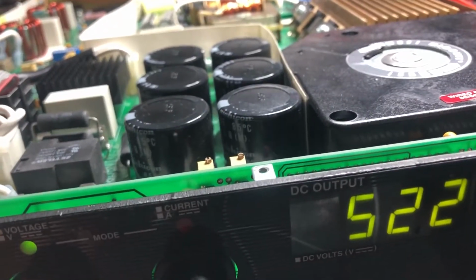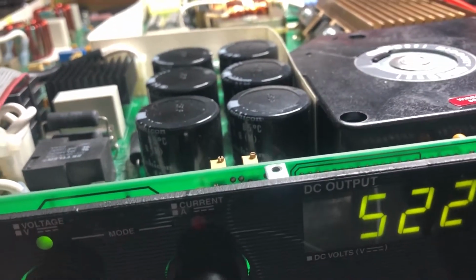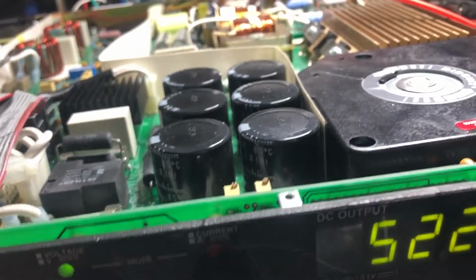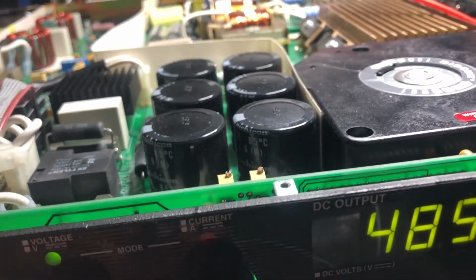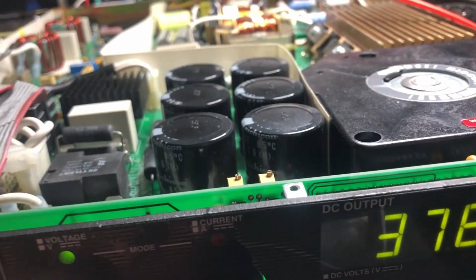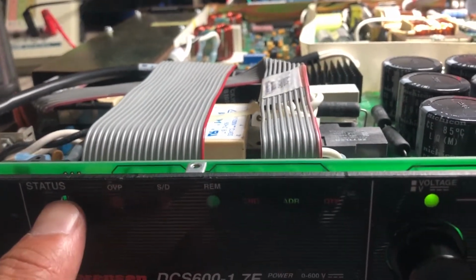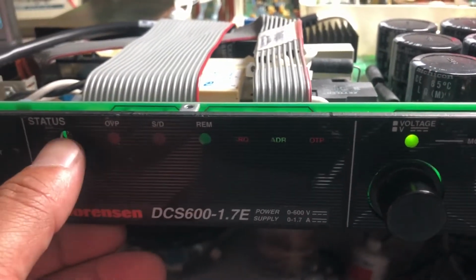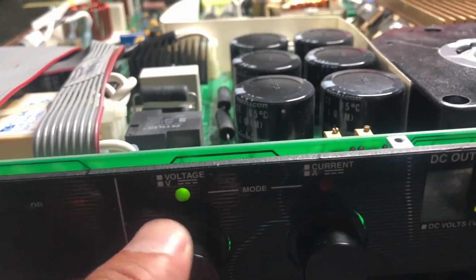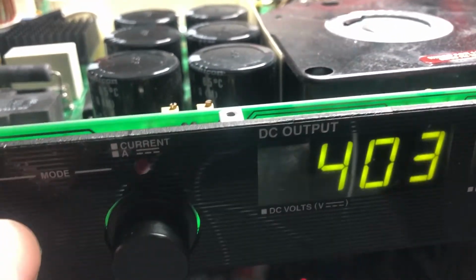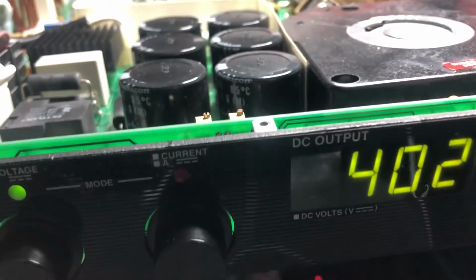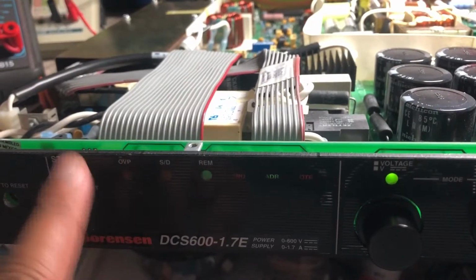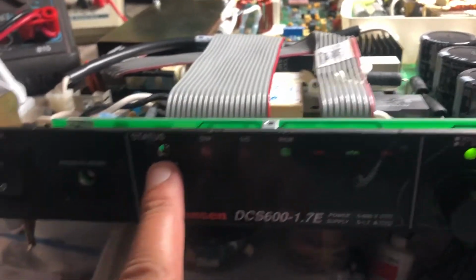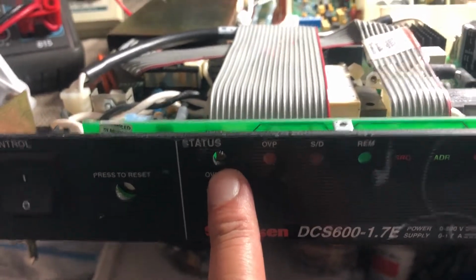This is useful in a scenario where you're doing some testing and your maximum voltage is supposed to be, say, only 200 volts. You set it to 200 volts on the main panel and then adjust the over voltage protection until it trips at that value, or slightly above it, to make sure your output never exceeds whatever you want. Otherwise, by accident, if somebody turns this, it can go above whatever value you want. So this is just an additional protection, but you need to be aware of this control, otherwise it can confuse you by shutting down the unit.